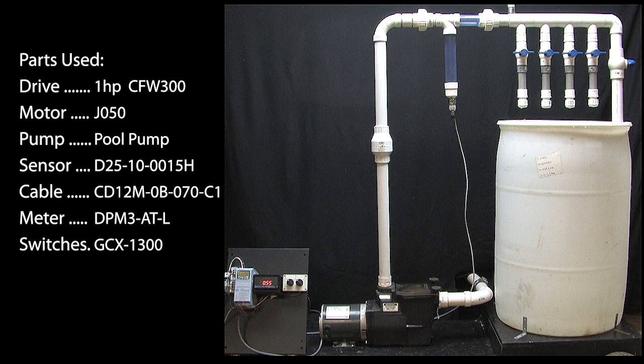The CFW300 drive does have a 10 volt output for powering sensors but this sensor needed at least 16 volts. We have two questions to answer.